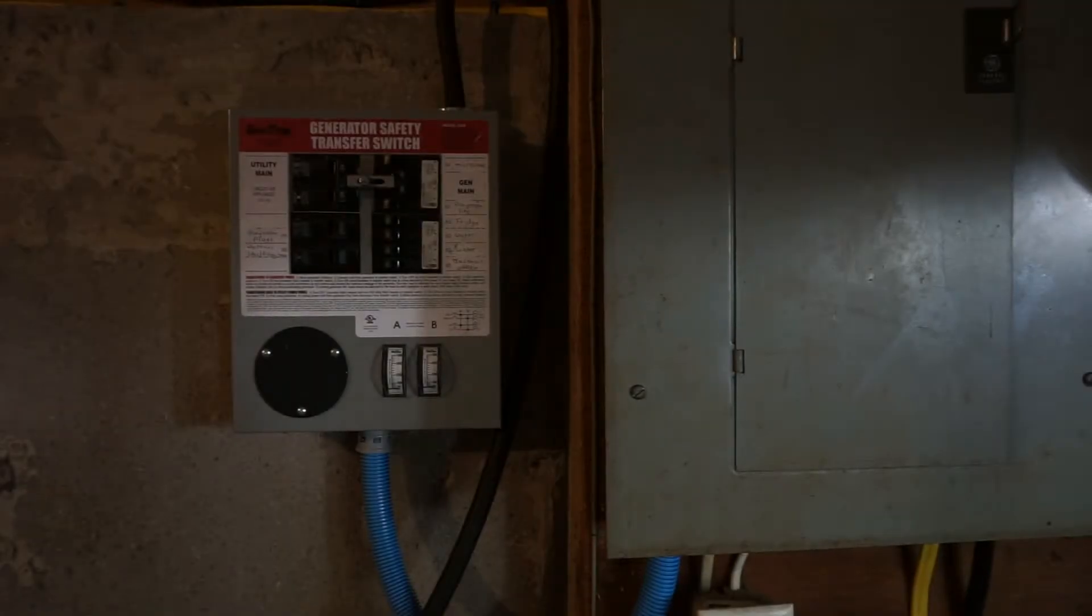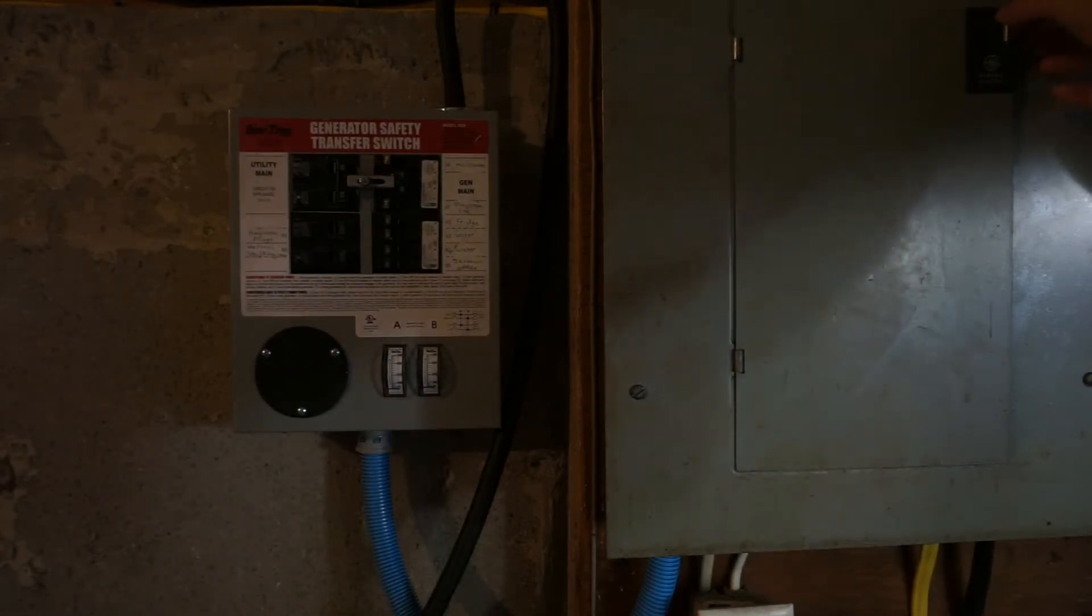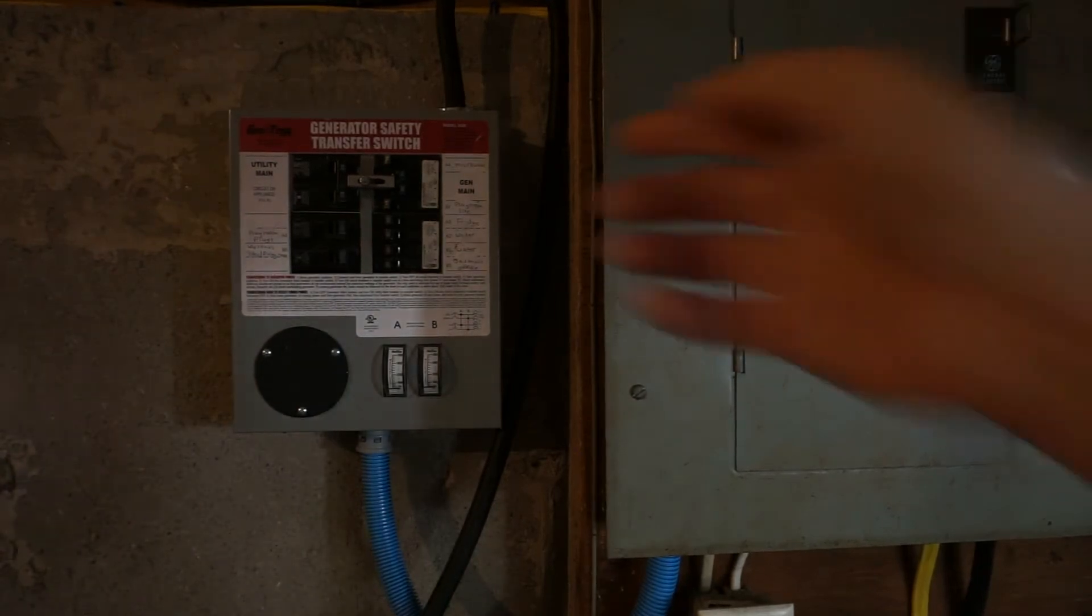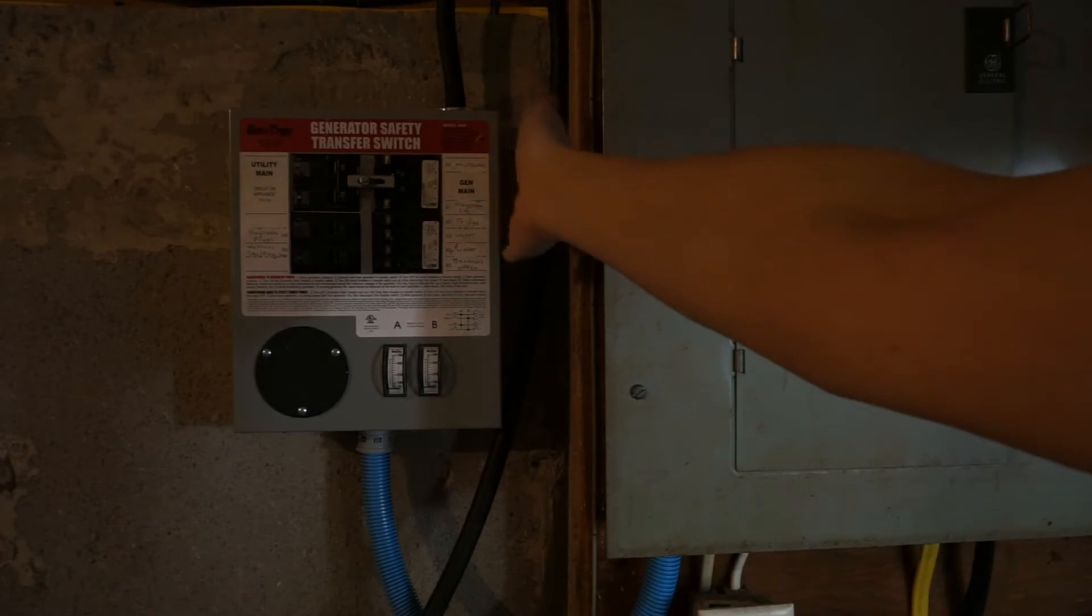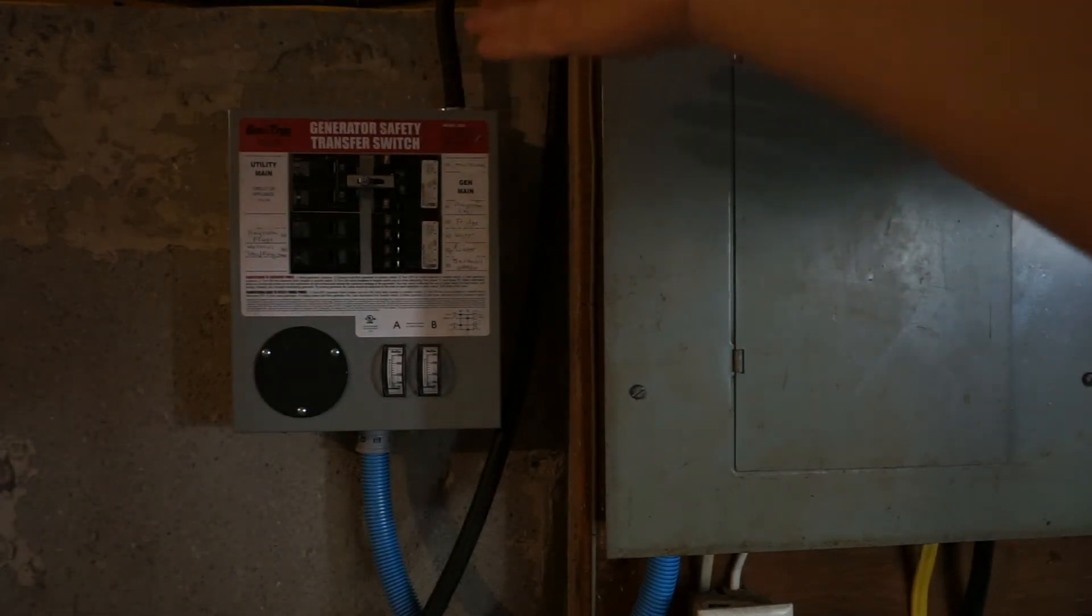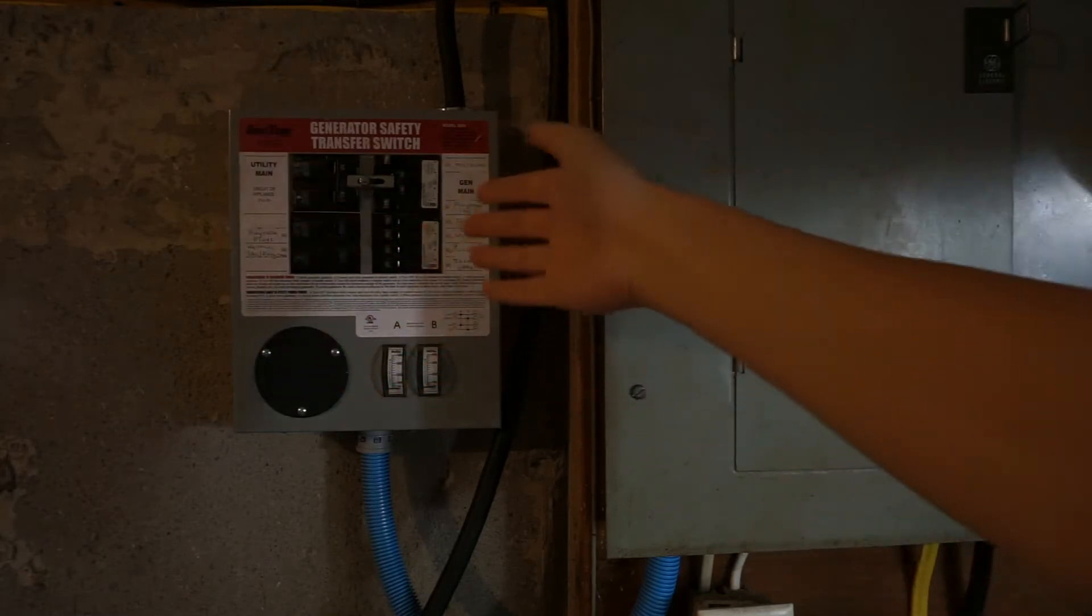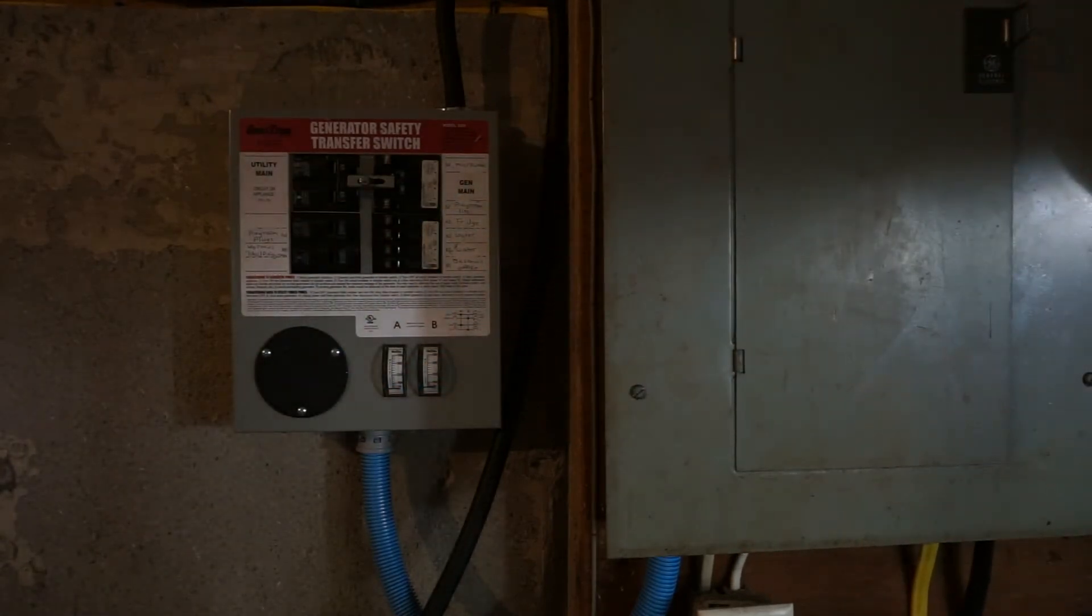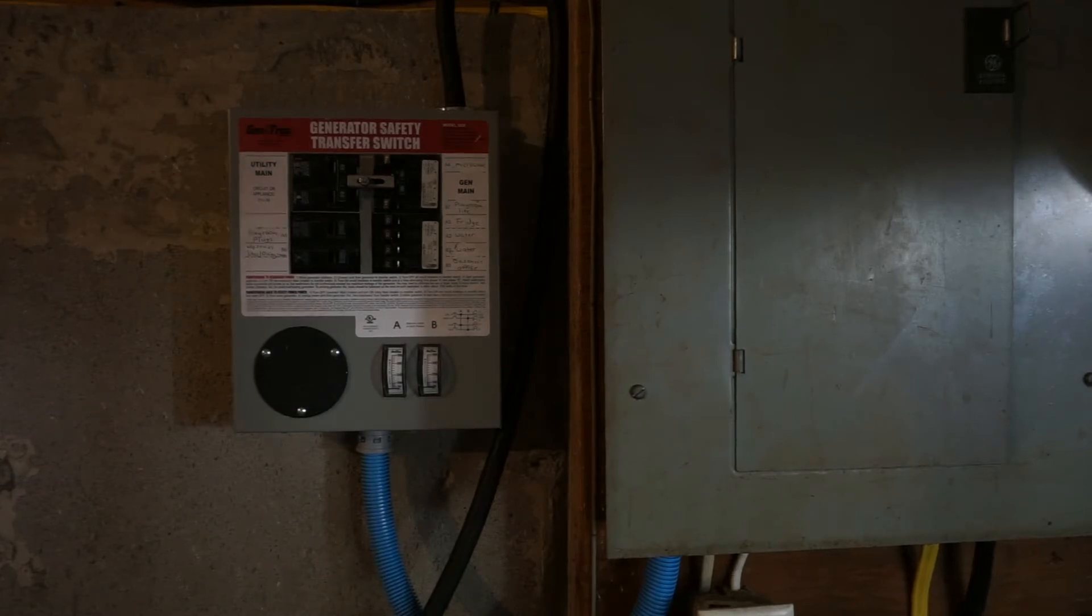And now we are in the garage and you can see here, to the right hand side, this is where the mains comes in from the utilities. And to the left, that's the transfer panel. So when the power goes off, I would flip the switch from using the mains to using a generator. So essentially that disconnects all the circuits tied to the subpanel from the mains. So that makes it safe to operate on your generator and inverters.